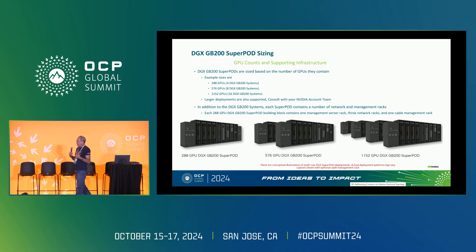People are deploying AI factories at various scales, in building blocks, at quantities of GPUs — all the way out to Elon talking about 100,000 or 300,000 — but they're just scalable elements that have all the same pieces. What would you do different if someone told you to design a 100-megawatt data center? The answer is it's not a 100-megawatt data center — it's 12 eight-megawatt data centers that really don't share anything other than the giant incoming power line. As a data center facility, hopefully that makes sense.